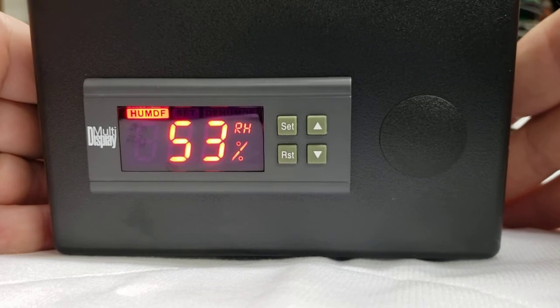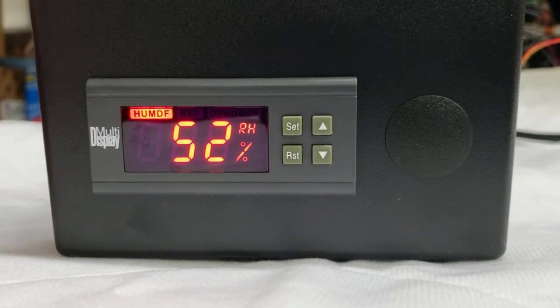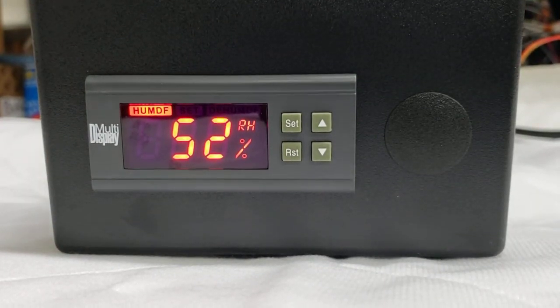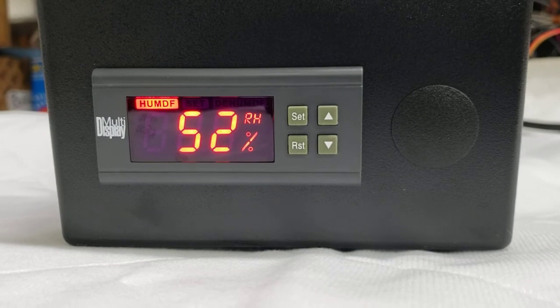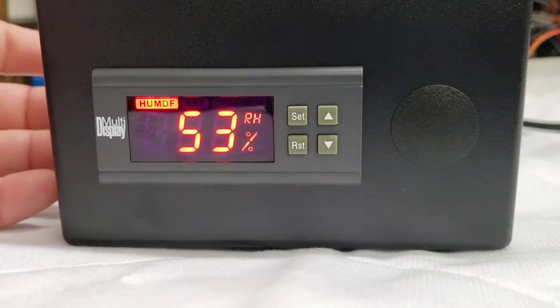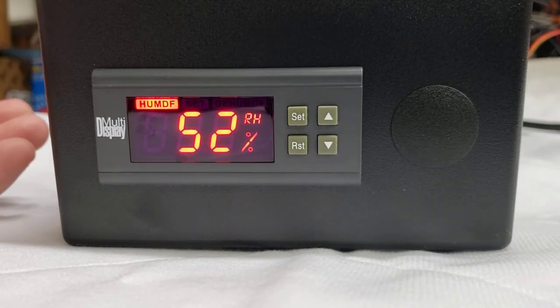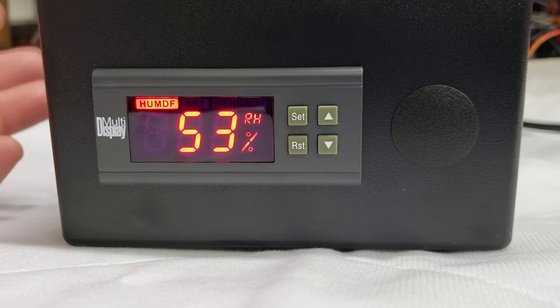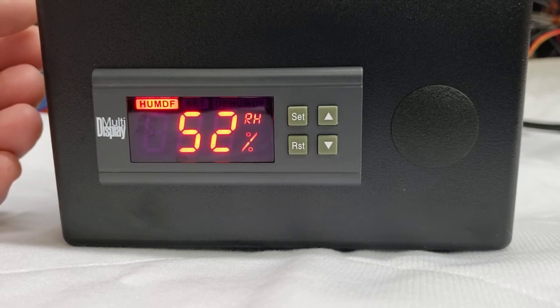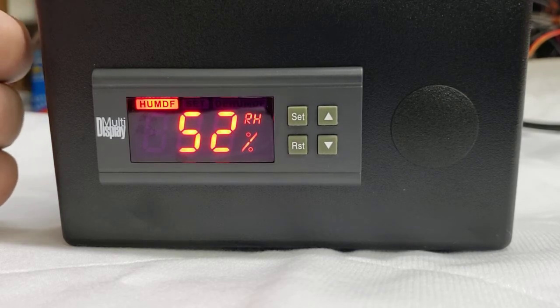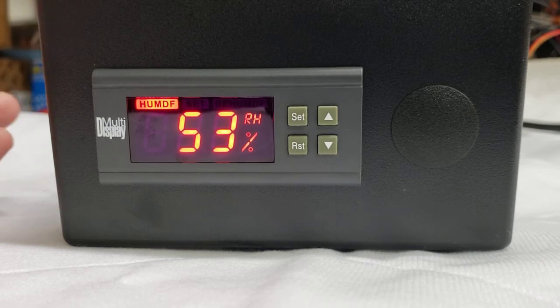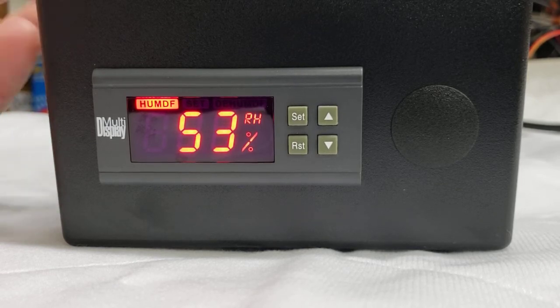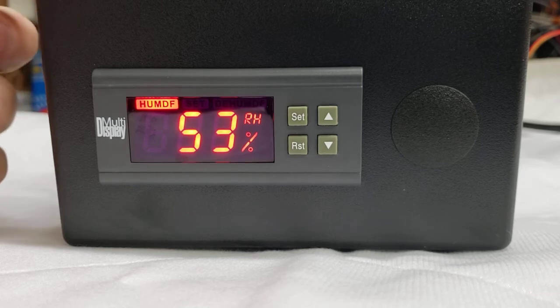It covers damage, including electrical damage or anything like that, and you want to make sure you keep your warranty intact. Now, our recommended setting for the humidity controller is 50%. A range of 40 to 60% is acceptable in an incubator, but we shoot for that target of 50. That humidity number is going to change constantly. It changes from within the environment, of course, with the incubator heater coming on and off, and even picking up slight variations in the temperature.